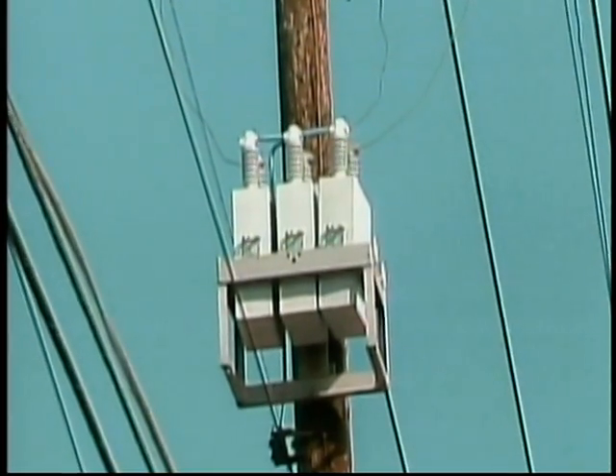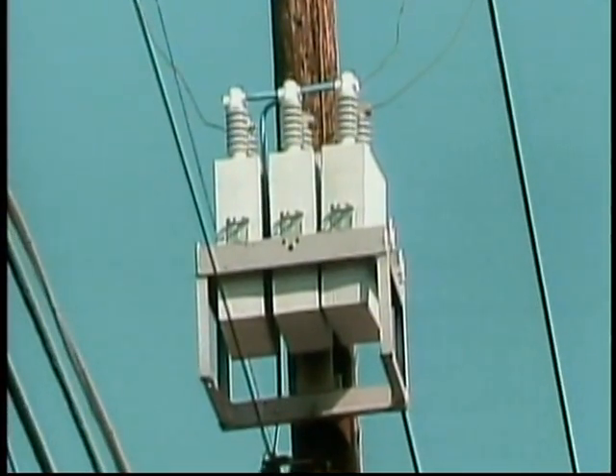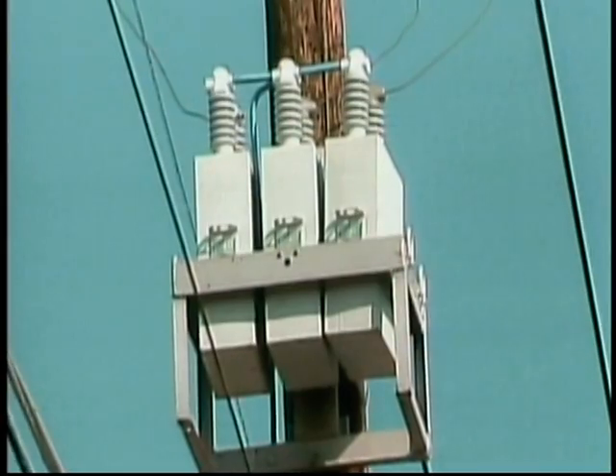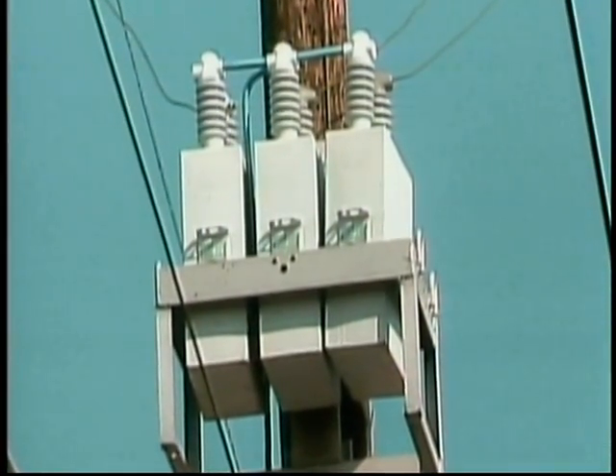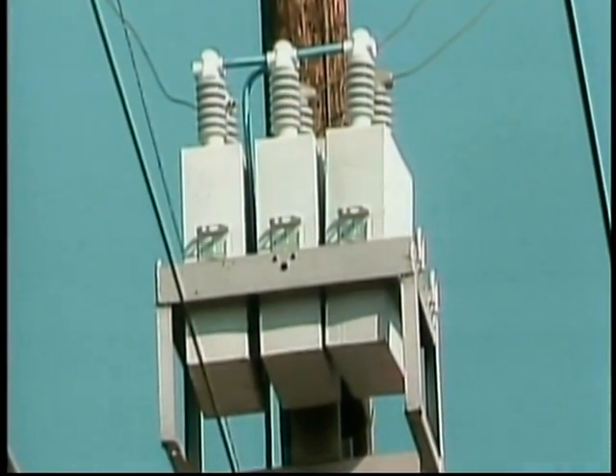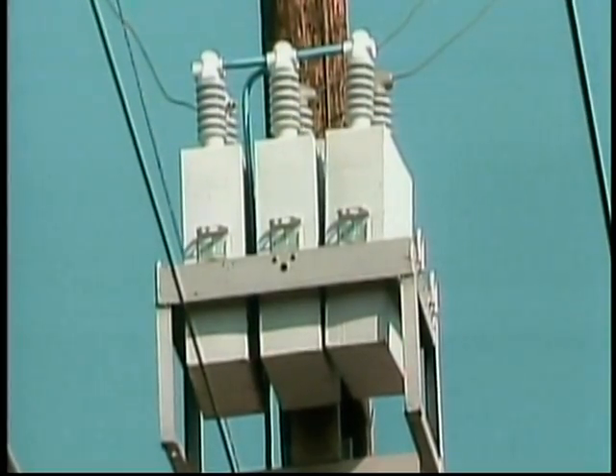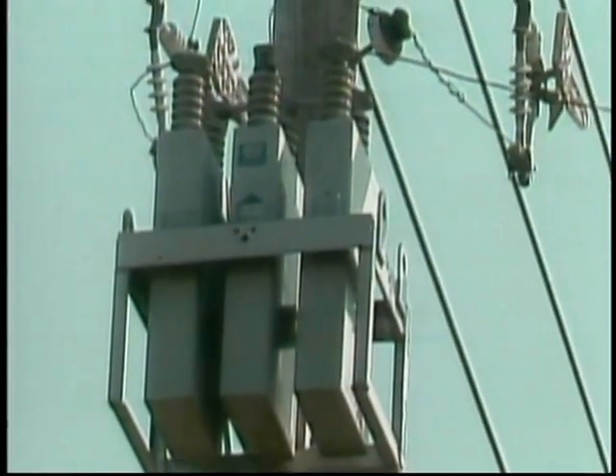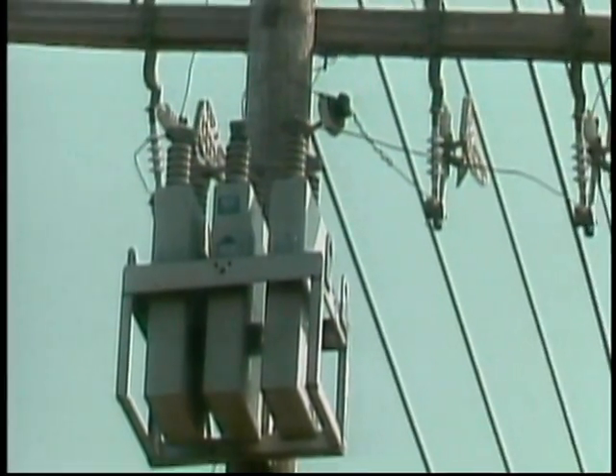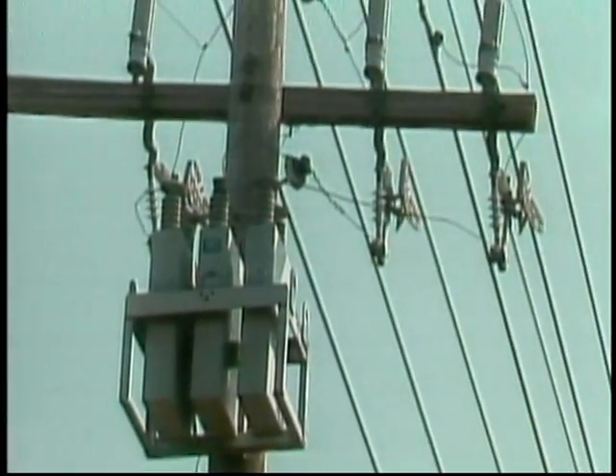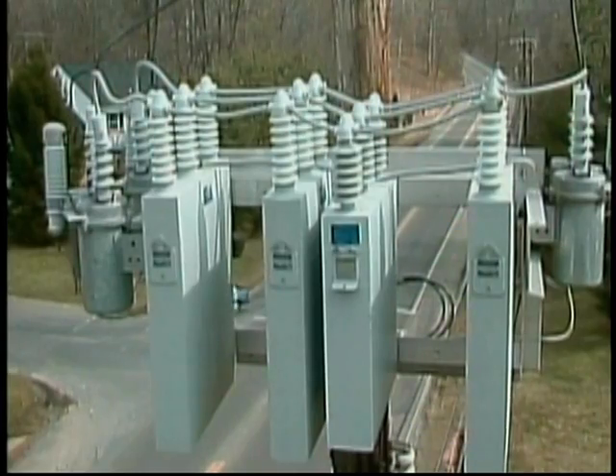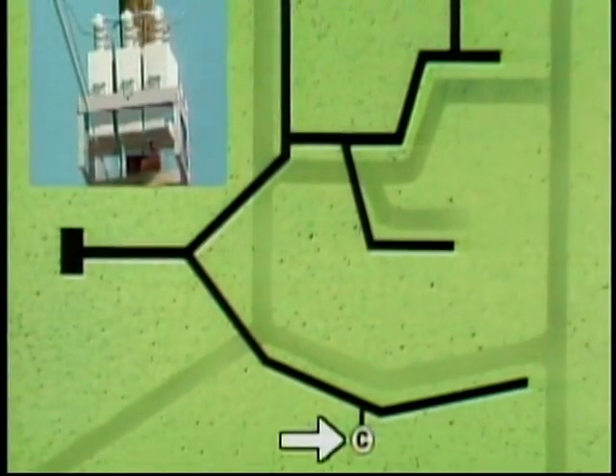Another device commonly found on overhead distribution poles is a capacitor. A capacitor is easily recognized by its square or rectangular shape. The number of bushings on a capacitor varies. The number of capacitors at a given location can also vary from a few capacitors to a bank of several capacitors. Capacitors can be found on any part of a distribution primary, but they're frequently located on circuits that feed inductive loads such as heavy-duty motors and air conditioners.